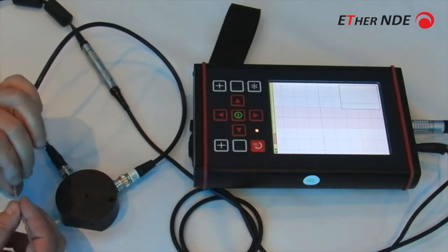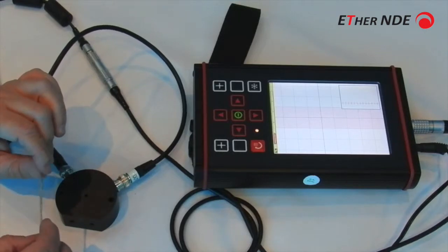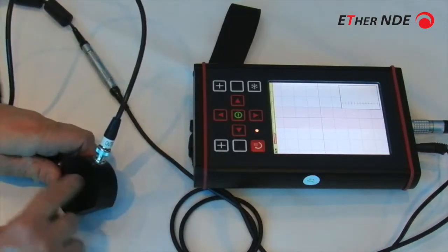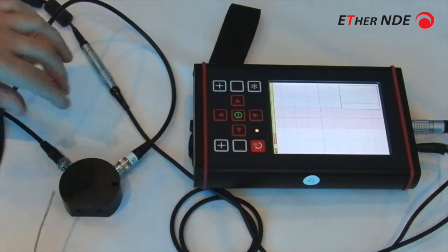And we've got some artificially introduced damage on the braid in two places. Now the coil is basically a differential pair, so two coils around the thing, comparing adjacent areas.